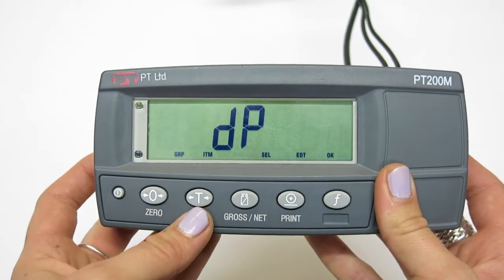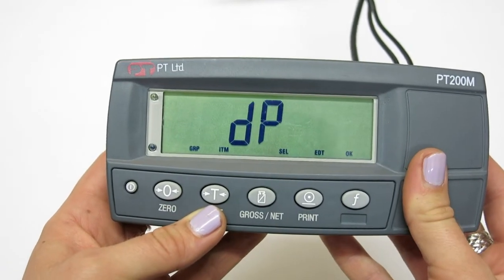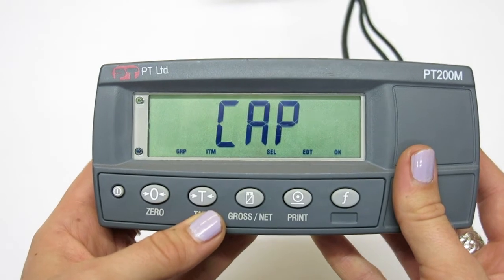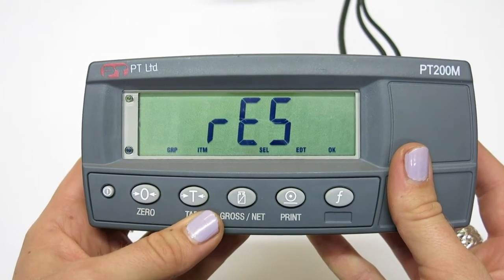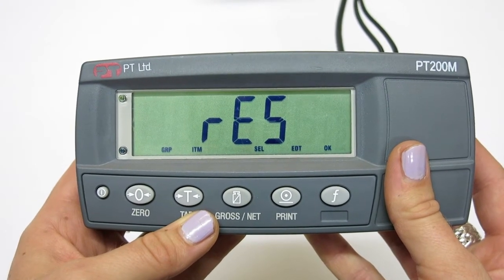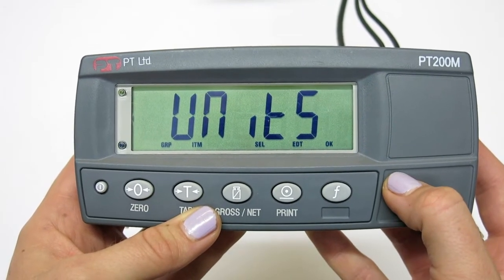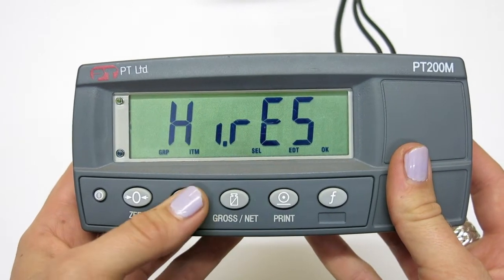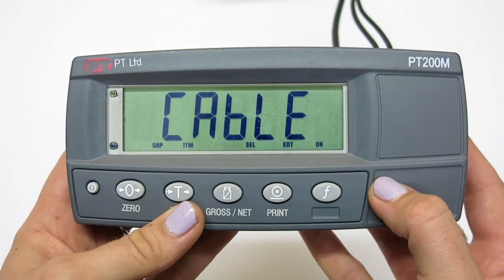Using the tare key to navigate, we have the options: DP which stands for decimal point position, CAP which stands for maximum capacity value, RES which is the resolution, the step number that the indicator counts by, UNITS is the units that you wish to measure the weight in, the option of high resolution or not, and Cable depending if you are using a 4 or 6 wire mode.